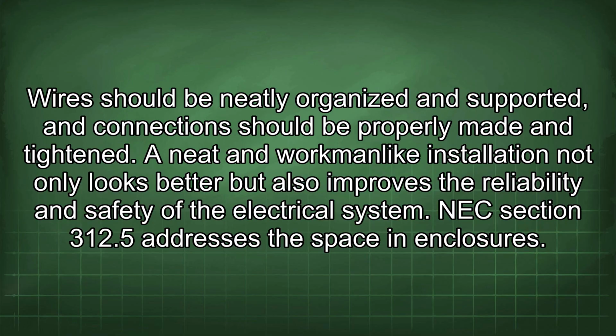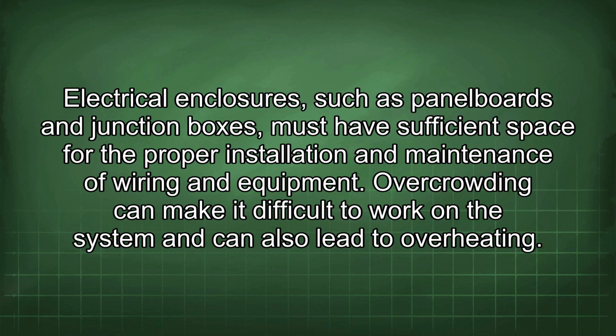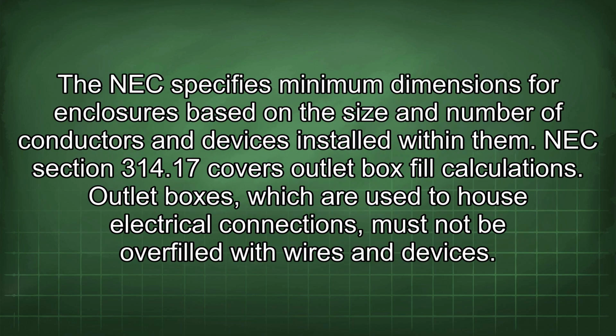NEC Section 312.5 addresses the space in enclosures. Electrical enclosures, such as panel boards and junction boxes, must have sufficient space for the proper installation and maintenance of wiring and equipment. Overcrowding can make it difficult to work on the system and can also lead to overheating. The NEC specifies minimum dimensions for enclosures based on the size and number of conductors and devices installed within them.